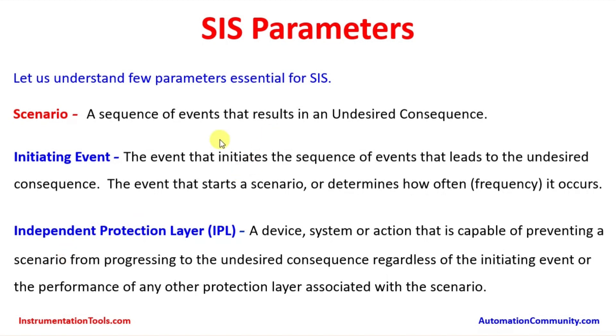The next parameter is Initiating Event — the event that initiates the sequence of events leading to the undesired consequence, or the event that starts the scenario and determines how often it occurs. For example, fuel gas pressure going high due to control valve failure is one scenario, and the control valve failure itself is the initiating event.